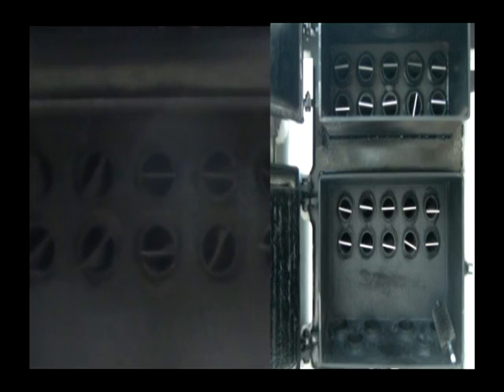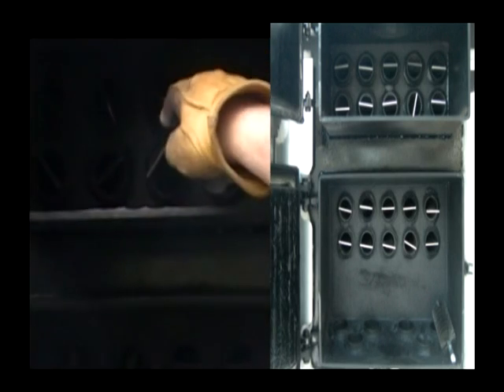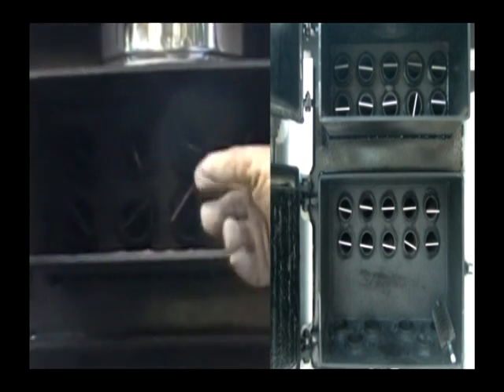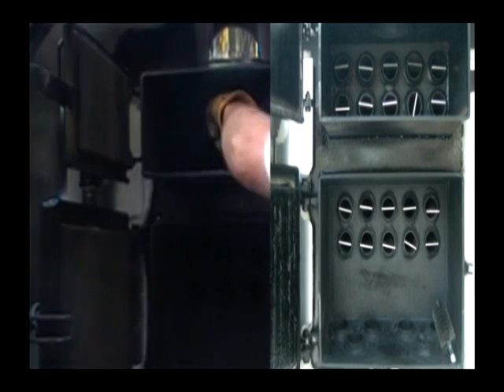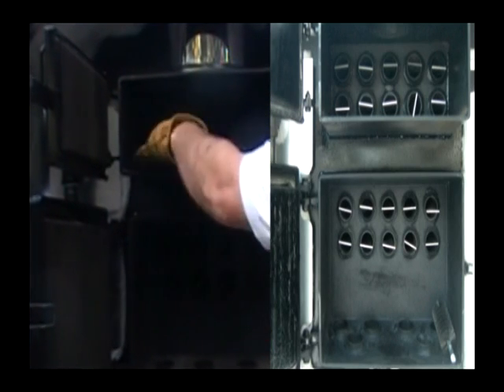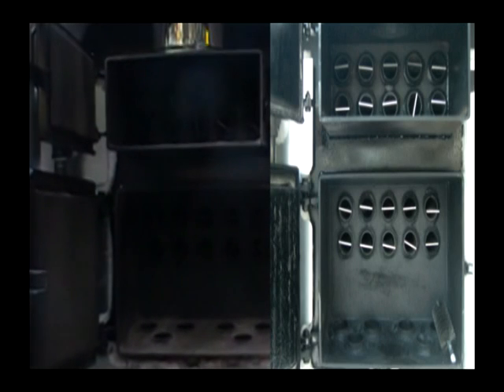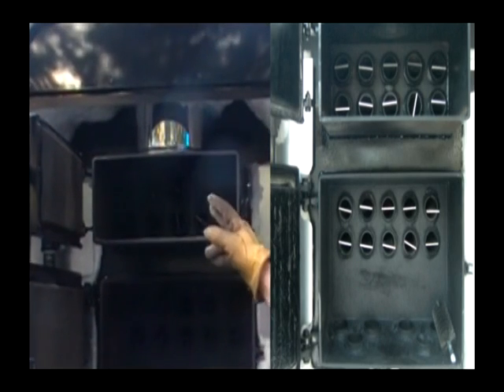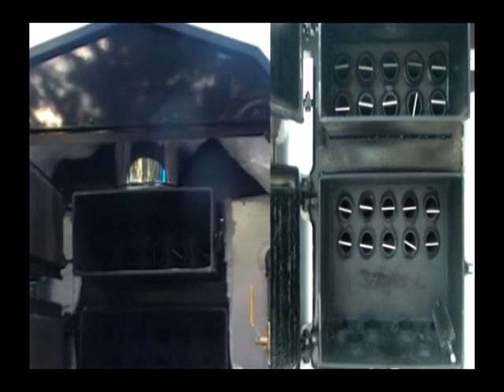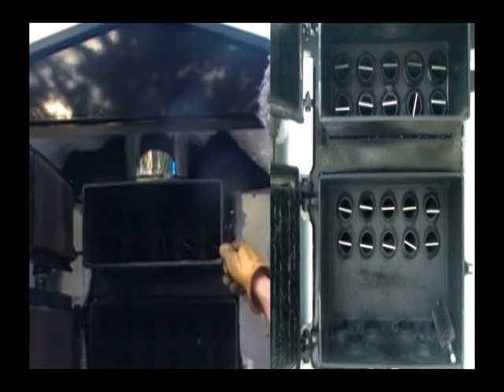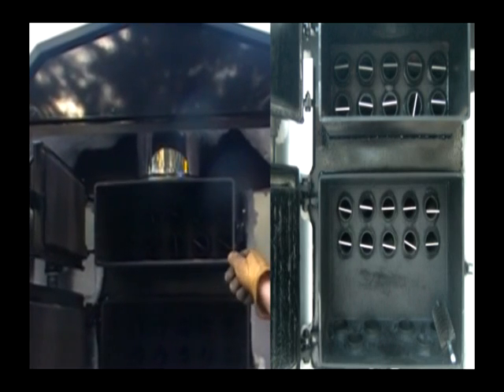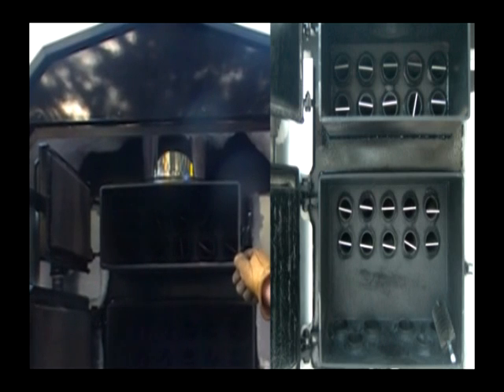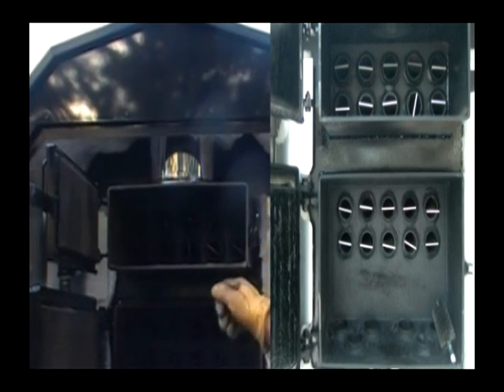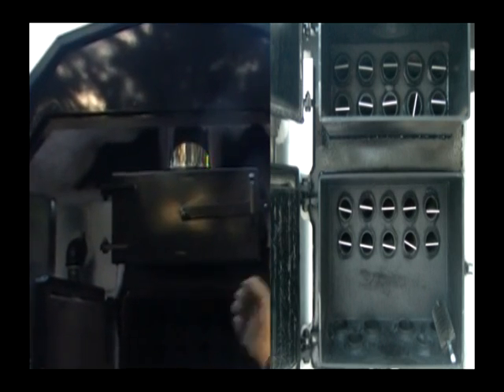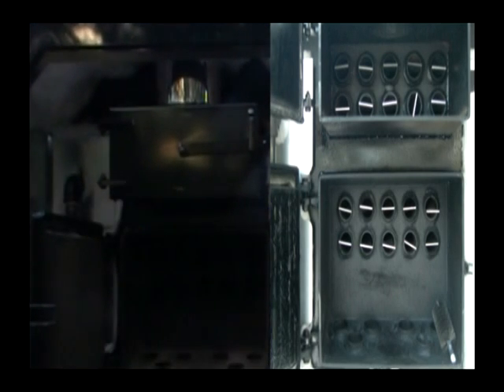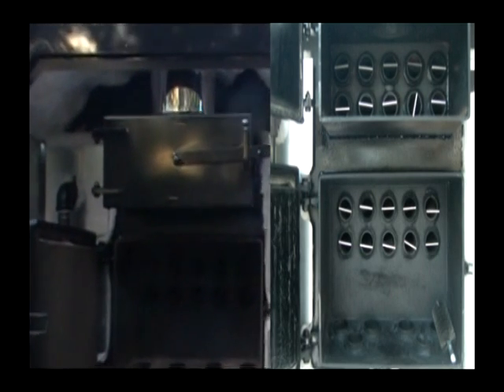At the front of the stove it does a 180-degree turn and comes to the back for the 4th pass of the heat exchanger before it goes up the stack. Again, turbulators in all the pipes. All you're getting is dust up there. Very easy to clean, very easy to access. Our temperature up in this chamber is always under 250 degrees Fahrenheit. It's constructed of 1/4 inch cold roll steel, double welded. Easy to access doors. We put the best gasket we could find on the doors. All the doors seal up very well. Adjustable latches again.